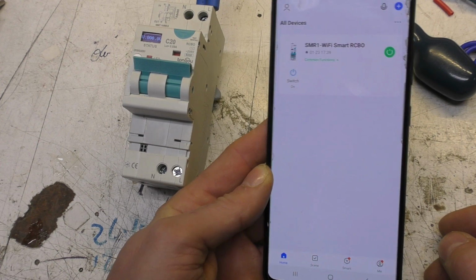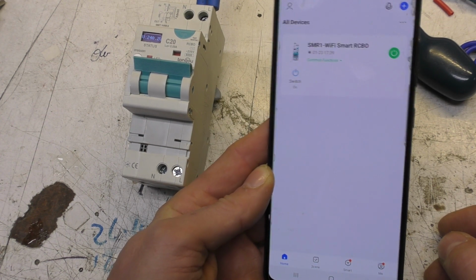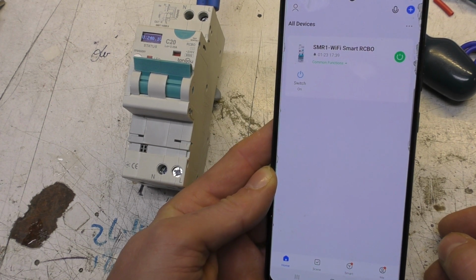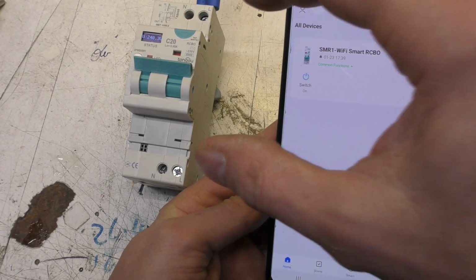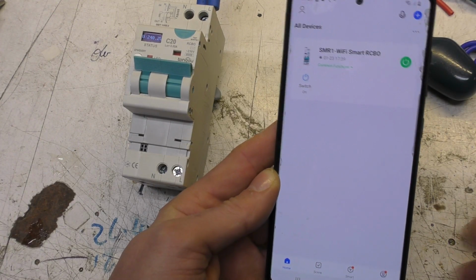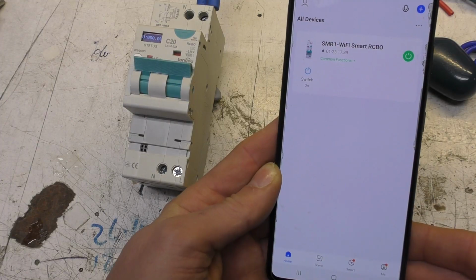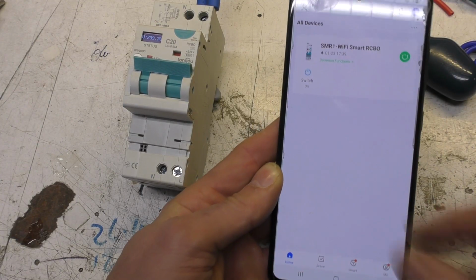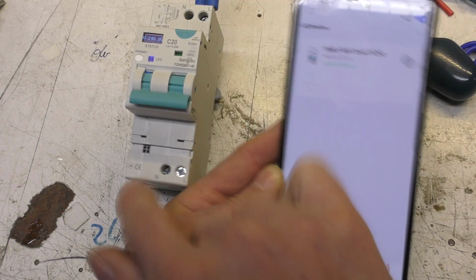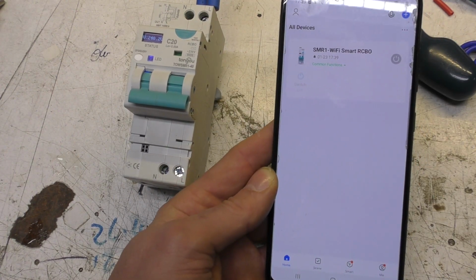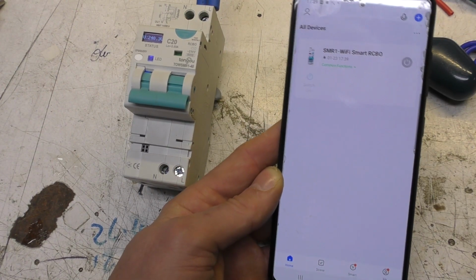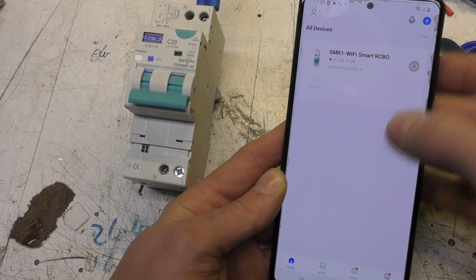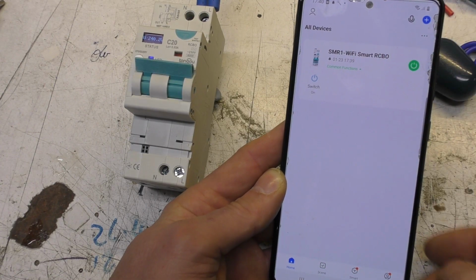Now, that alone makes it a dangerous, stupid idea, because you have something sitting in a distribution board which looks, to all intents and purposes, like a normal circuit breaker. So, for example, someone doing maintenance might come along, okay, fine, we need to do some work on it, turn it off. It's a double pole breaker, so I've isolated live and neutral, fine, we're now safe to work on it. And then someone who's sat on the end of this circuit says, well, why's my circuit breaker gone off? Let's see what's going on.